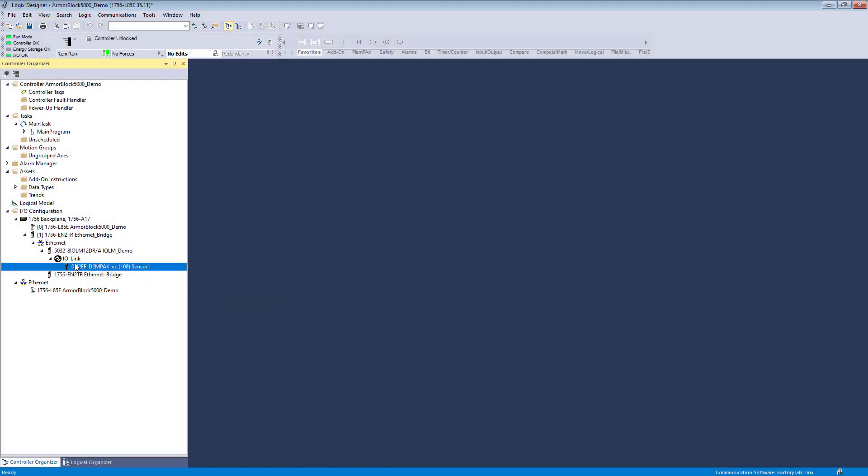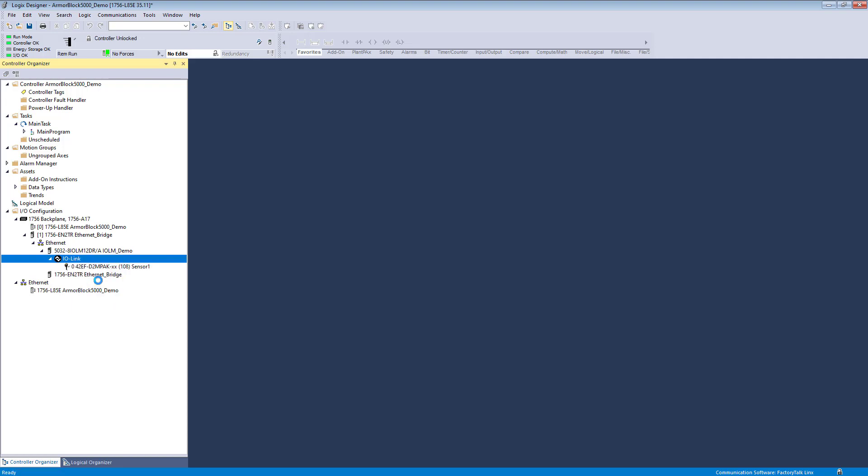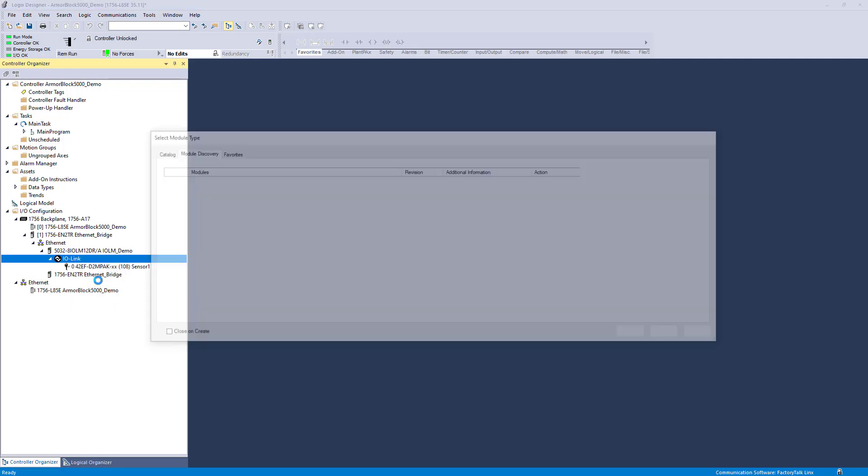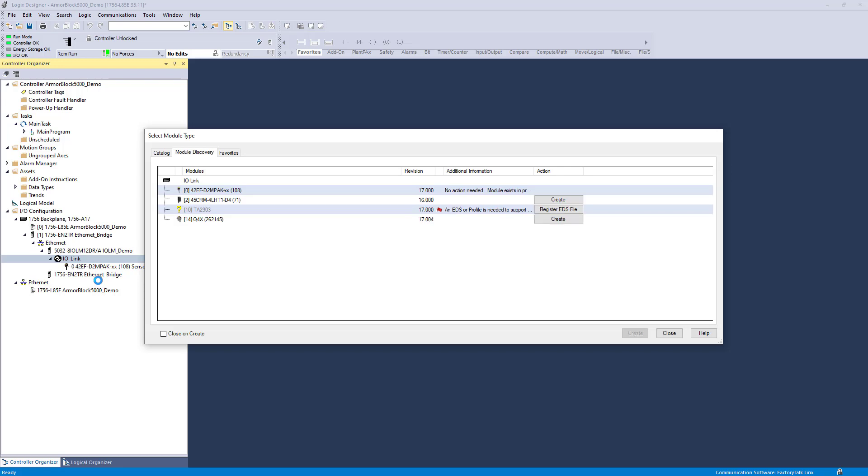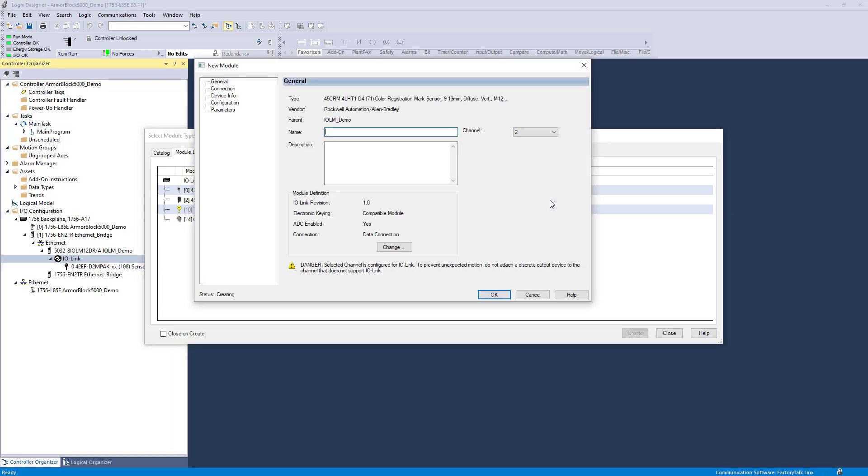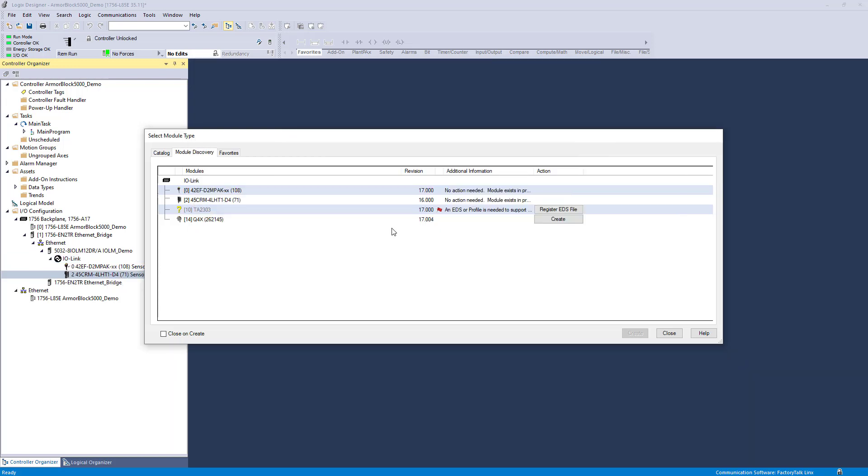Another method to add devices is via the Module Discovery Tool. Right-click on the IO-Link bus icon in the IO configuration tree and select Discover Modules. With this tool, the IO-Link Master Block scans for connected IO-Link devices and allows you to add the devices to its configuration tree. You can add devices like how we did for the first IO-Link device.